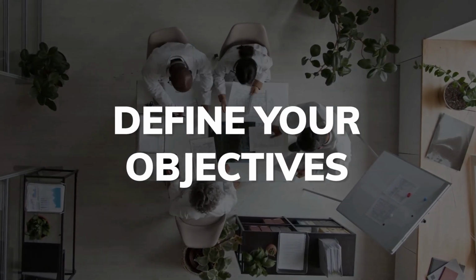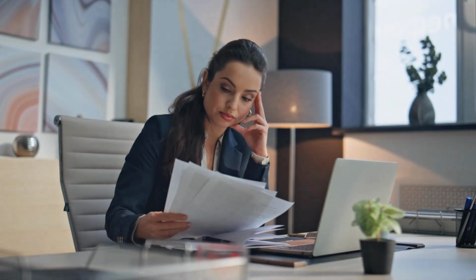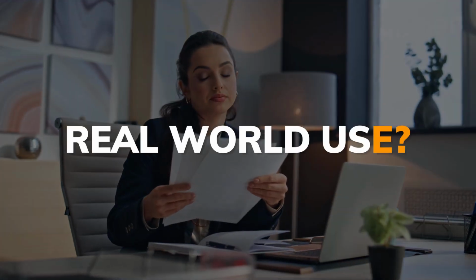Before anything else, you need to define your survey objectives, and it's worth taking a step back to explain what that actually means. So your PMCF survey objectives are the specific questions you are trying to answer through your data collection. What do you still need to know about your device in real-world use?